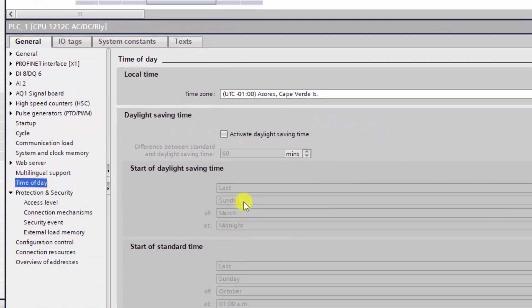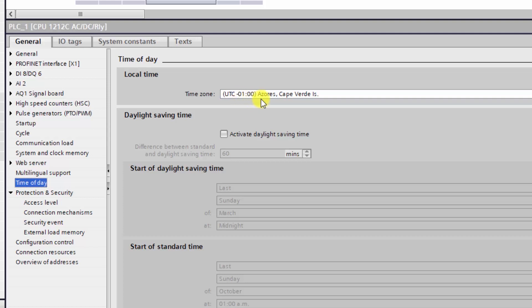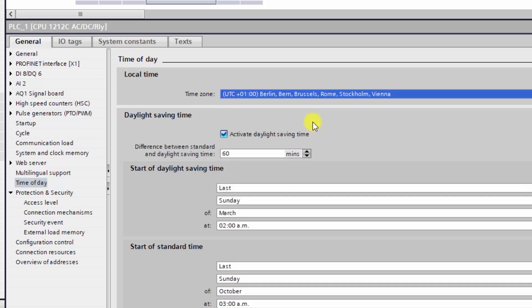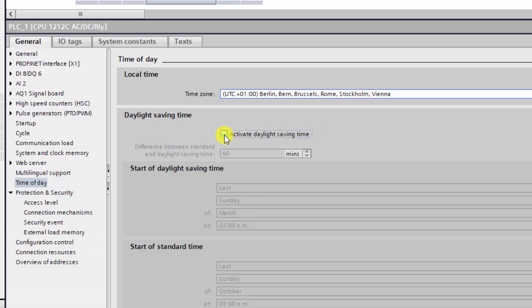To do this, we can enter to the hardware configuration and then enter to the properties of the controller. Next, click on the sub-menu Time of Day. There you will find as default a time zone which is UTC minus one and without the DST. To have a correct local time, you should modify this parameter depending on your time zone. For example, if you are in Berlin, then your time zone parameter should be set to UTC plus one. And let's suppose that Berlin does not apply the daylight saving time.